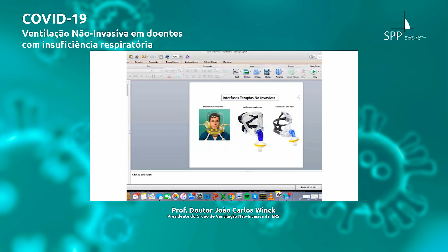Okay, bi-level. So if I come back to this slide, with this setup here, you would not recommend to perform CPAP. I don't hear you. So with this setup here, you don't recommend to use CPAP as the mode of ventilation, right? No. If you want to use this, you have to add 5 of pressure support at least.